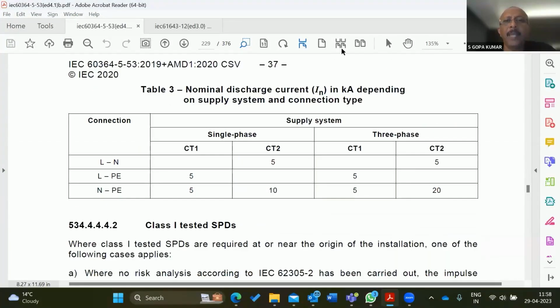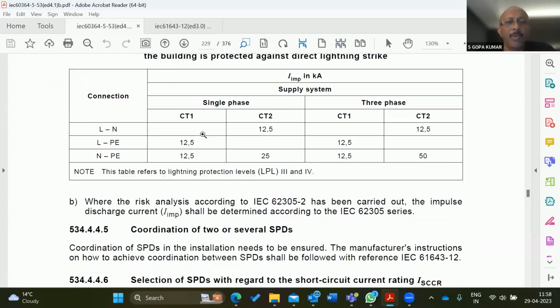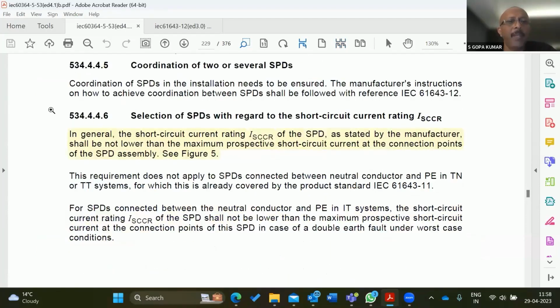Several selection methods are explained. I don't want to go through the whole thing; I will show you some important measures. For example, selection of SPDs with regard to the short circuit current rating I SCCR. In general, a short circuit current rating I SCCR of the SPD, as stated by the manufacturer, shall not be lower than the maximum prospective short circuit current at the connection point of the SPD assembly.